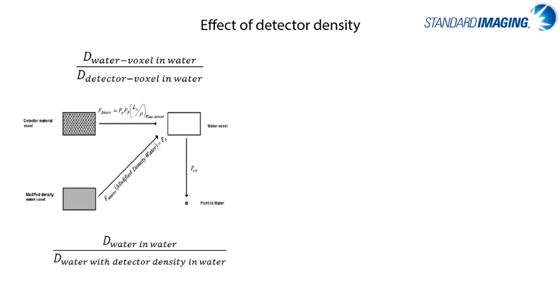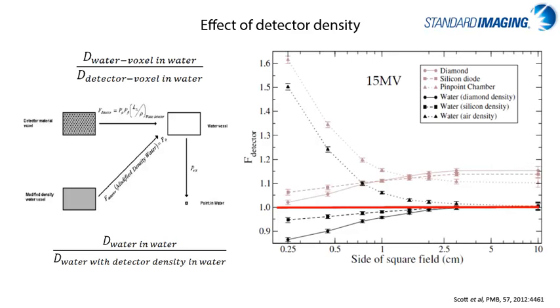This graph shows a Monte Carlo study of the influence of the detector composition as a function of field size, and it is clear by first looking at the tan lines in this graph that the traditional detectors, especially the ion chambers, have a substantial effect in small fields less than 2 cm² because of the non-water equivalence of their components. The diamond and diode detectors are better, although there is still up to a 10% effect at very, very small field sizes.